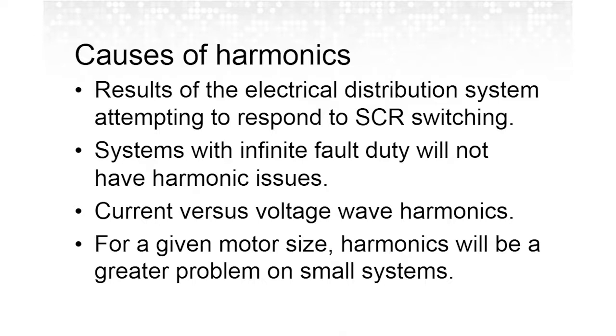If you ever look into harmonic issues, I've written a couple of articles in CSE that you can look up. The smaller distribution systems have much more impact from harmonics than the larger systems do. As long as you can keep the harmonics as part of the current wave harmonics, those really don't bother anything other than maybe some wire heating or transformer heating. It's the voltage wave harmonics that are the problem. So whenever you're having them metered, you should meter for voltage wave harmonics to determine whether your total harmonic distortion is a problem or not.